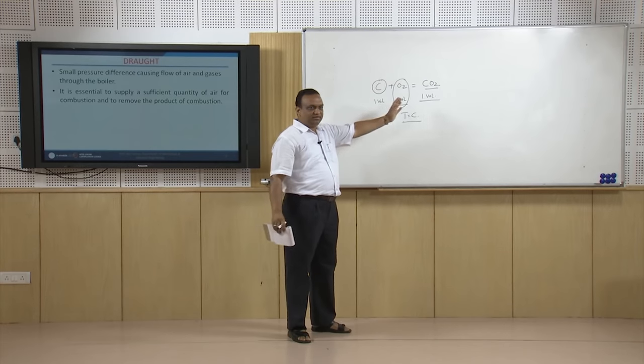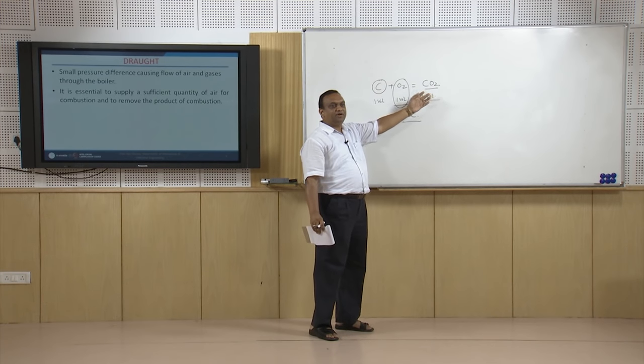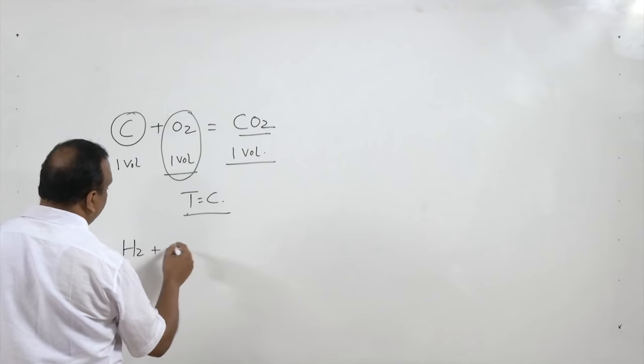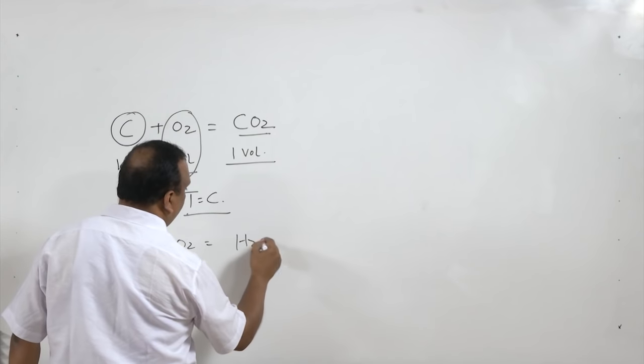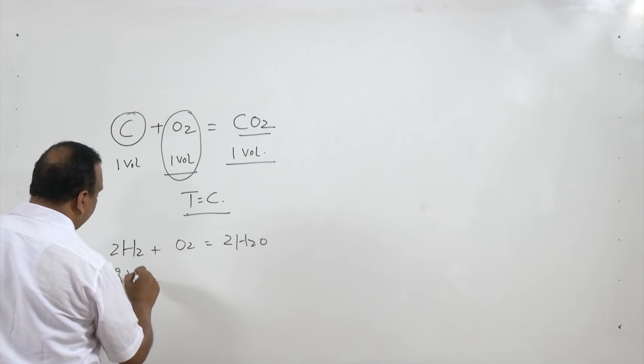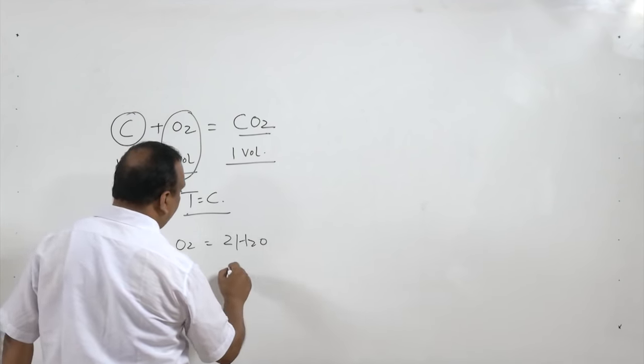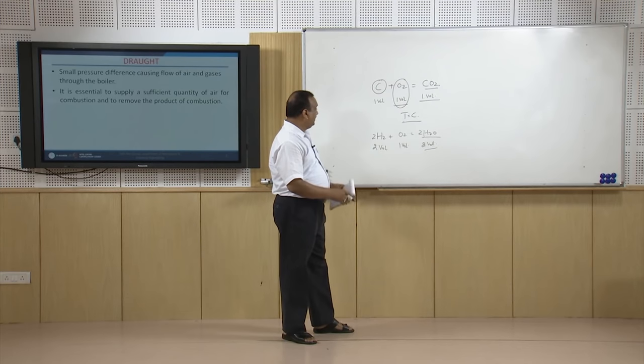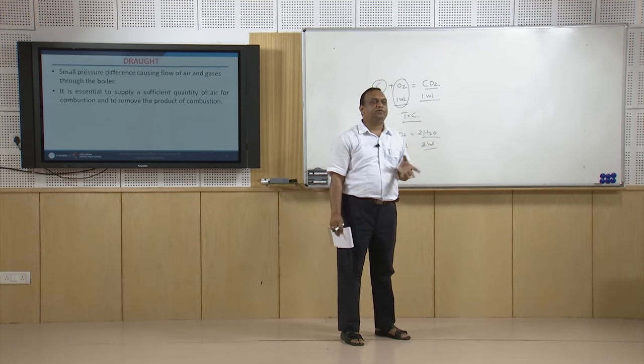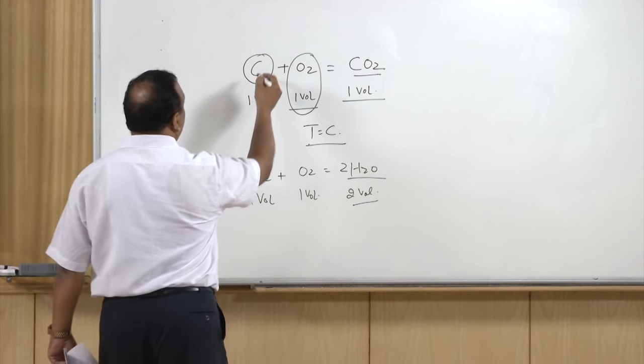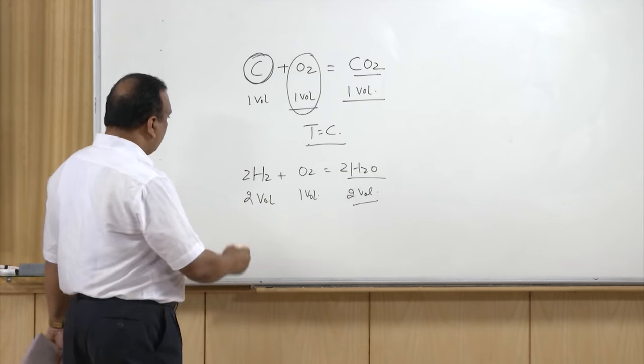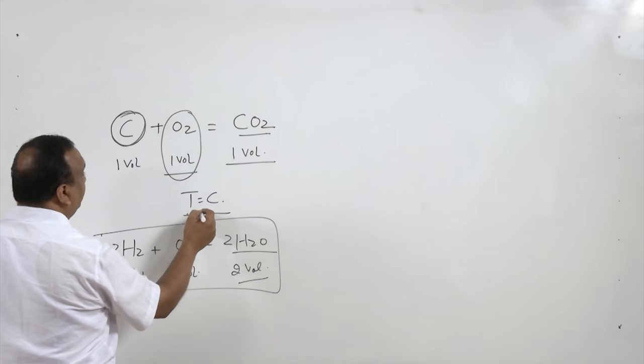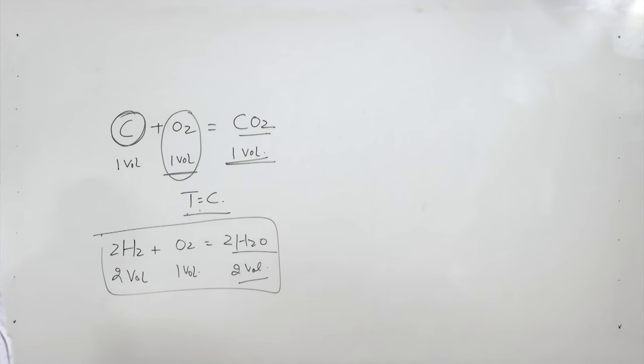If temperature differs, volume will vary. For hydrogen, 2H₂ + O₂ → 2H₂O, but hydrogen is only 4–5% of fuel, so it is not significant. The dominant component is carbon. Therefore, for chimney height calculations we assume that at the same temperature, the volume of air equals the volume of flue gases. Since density is a function of temperature, we use a reference density at 0°C (273 K) and pressure 101.3 kPa.